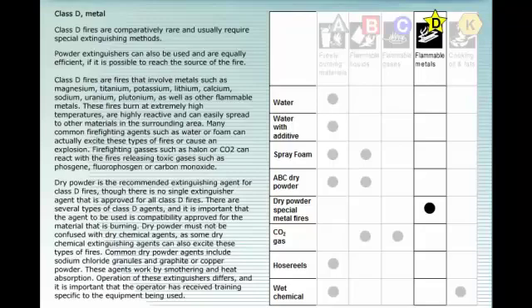Common dry powder agents include sodium chloride granules and graphite or copper powder. These agents work by smothering and heat absorption. Operation of these extinguishers differs, and it is important that the operator has received training specific to the equipment being used.